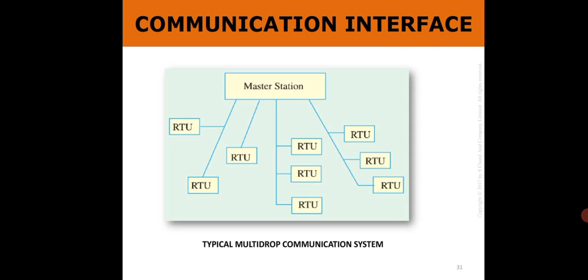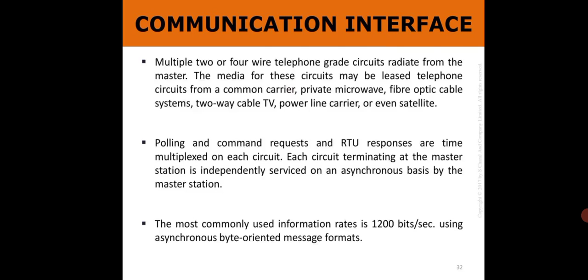Multiple 2 or 4 wire telephone grade circuits radiate from the master. The media for this circuit may be leased telephone circuit from a common carrier, private microwave, fiber optic cable system, two-way cable TV, power line carrier, or even satellite. Polling and command requests and RTU responses are time multiplexed on each circuit. Each circuit terminating at the master station is independently serviced on an asynchronous basis by the master station. The most commonly used information rate is 1200 bits per second using asynchronous byte-oriented message formats.